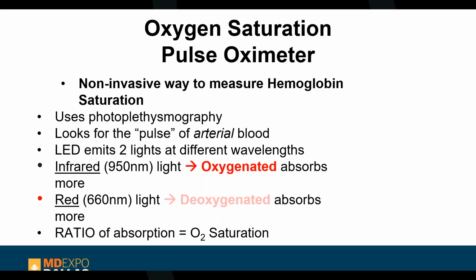Next vital sign is the pulse oximeter. And this is when I was asking about the different wavelengths, the red and the infrared. It's a non-invasive way to measure hemoglobin oxygenation. It uses my favorite word, PPG, photoplethysmography. It looks for the pulse of the arterial blood and emits two different LED lights, red and infrared. Oxygenated blood absorbs more of the infrared, and deoxygenated blood absorbs more of the red light. So there's a lot of variables in pulse oximeters too, kind of like blood pressure, but not quite as many as blood pressure. The ratio of absorption equals the oxygen saturation, or O2 sat.